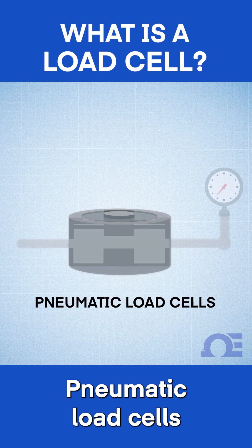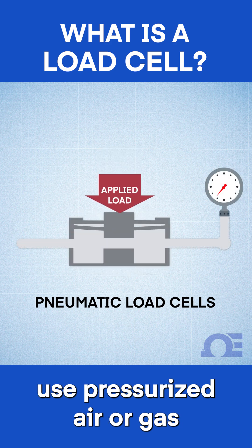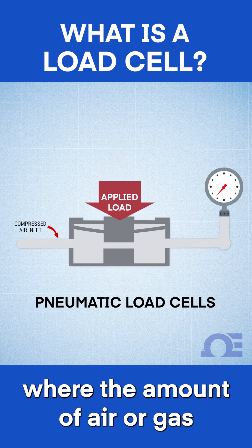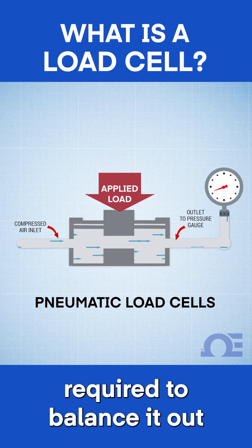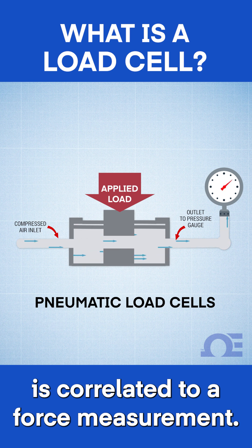Pneumatic load cells use pressurized air or gas to balance out the applied weight, where the amount of air or gas required to balance it out is correlated to a force measurement.